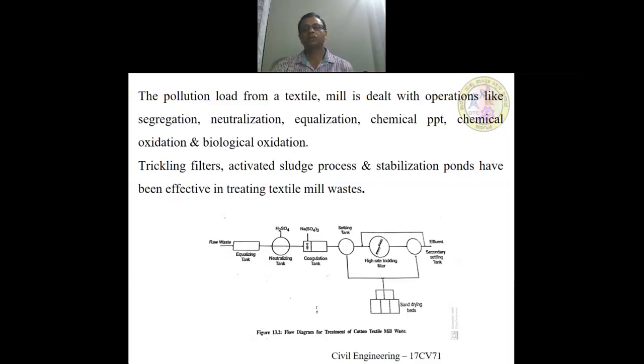Then you add a coagulant and go for the coagulation process, where you settle the fiber particles. Next is the settling tank, where the particles settle, so we remove inorganic substances by adding coagulants. Then the remaining BOD goes to trickling filters, generally a high rate trickling filter, then the effluent is discharged.